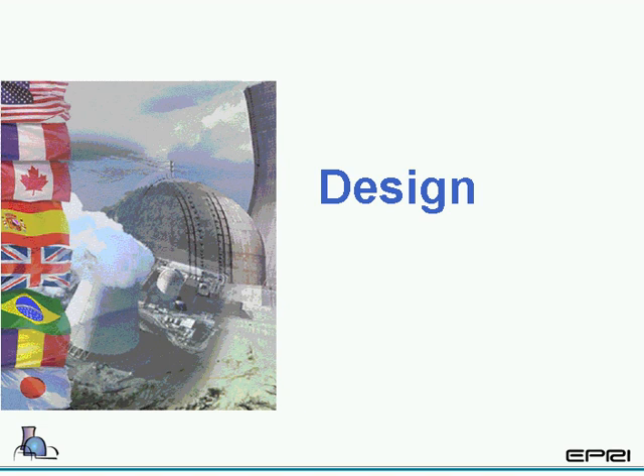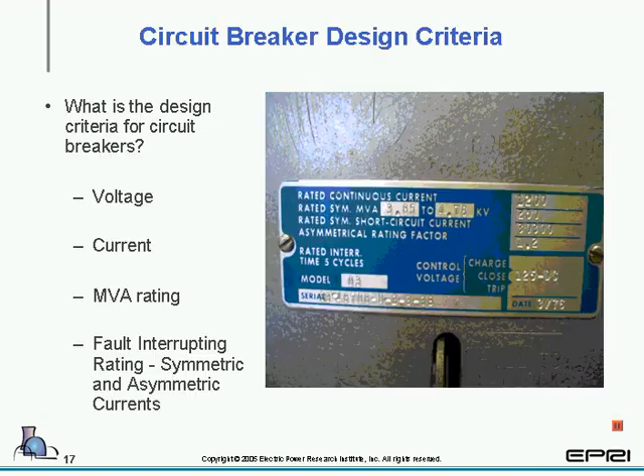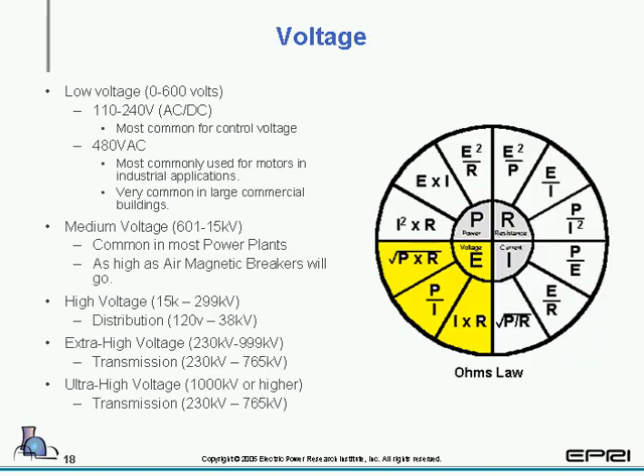That pretty much concludes how the zones of protection are set up. Now we're going to start taking a look at how the breakers are designed. Circuit breaker design criteria. There are 4 major ones: voltage, current, MVA rating, and fault interrupting rating, symmetrical and asymmetrical current. Two of the main ones, as far as technicians are concerned, that need to be paid attention to are the voltage and current. Normally your MVA ratings and fault interruptions are set through ANSI and IEEE standards and are pretty generic amongst all breakers. But you'll see later on where voltage and current will matter. And we're going to take a look at those now.